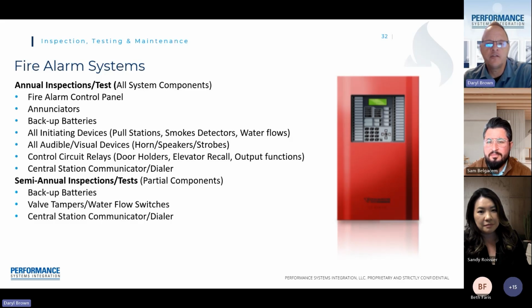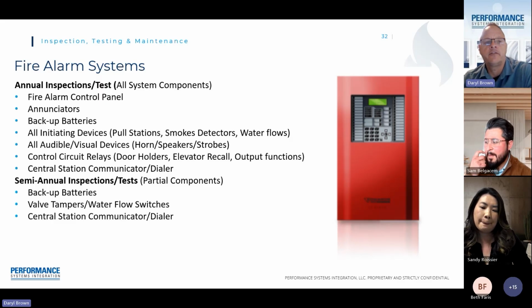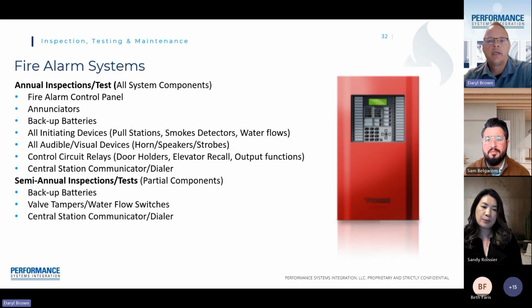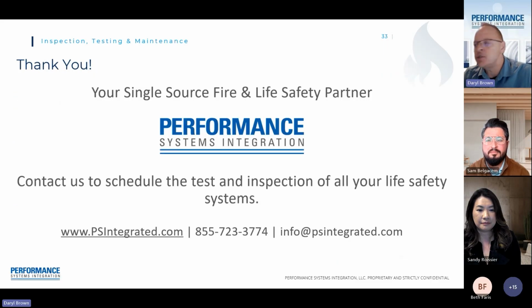So that's something to consider when you're choosing your vendors, especially when you're doing residential. When we're going into units, we have to look at sprinkler heads once a year as part of sprinkler inspections. We also have to test horns inside units once a year. So if you're doing those together, then we're going in there one time and satisfying both requirements, NFPA 25 and NFPA 72. That's the end of our presentation. I want to see if there are any questions.